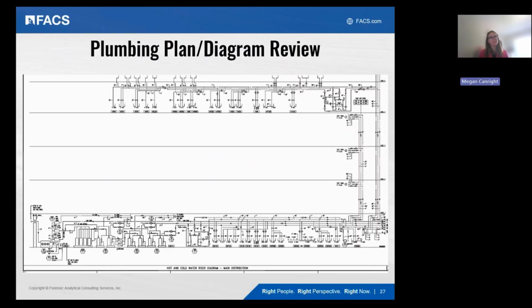This is an example of a riser diagram. Riser diagrams are extremely useful for understanding the building water system—they give a one-stop picture of how water flows into the building, how it's processed, tempered, and heated, and how it gets out to various floors and fixtures. Plumbing diagrams can help identify dead legs, shell spaces that aren't built out, and areas of future tie-in. We can easily see how many water heaters there are and what types. These riser diagrams, plumbing diagrams, and fixture schedules can be really helpful before you even step on site.